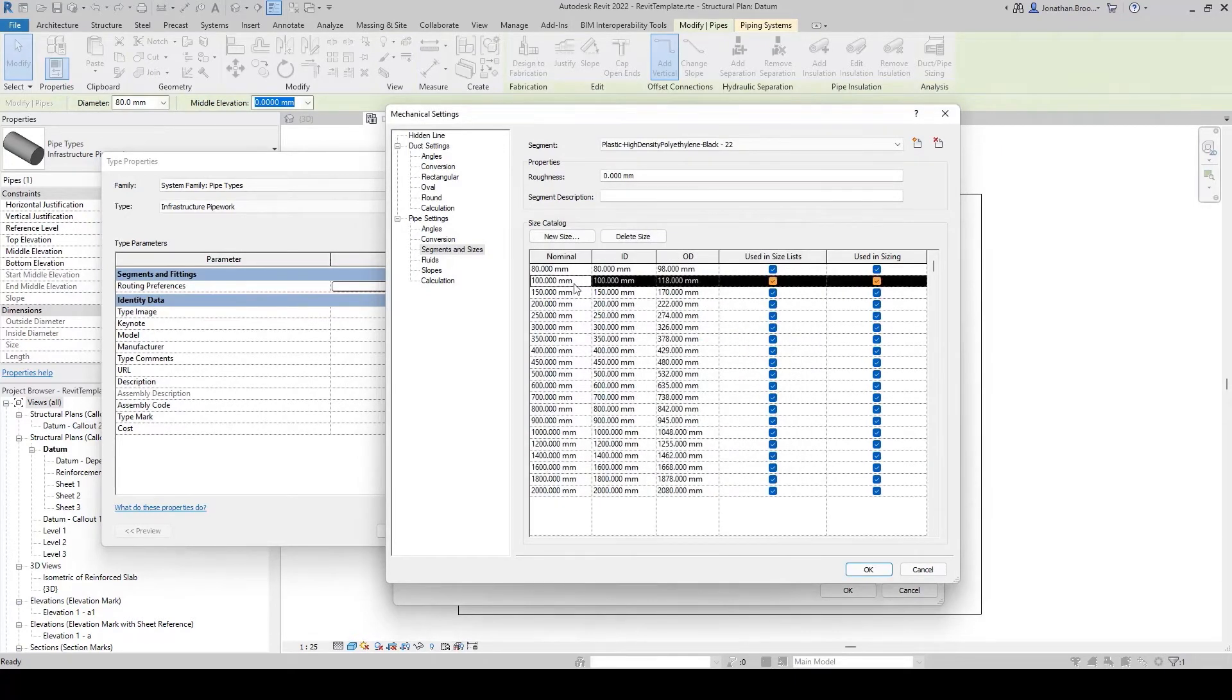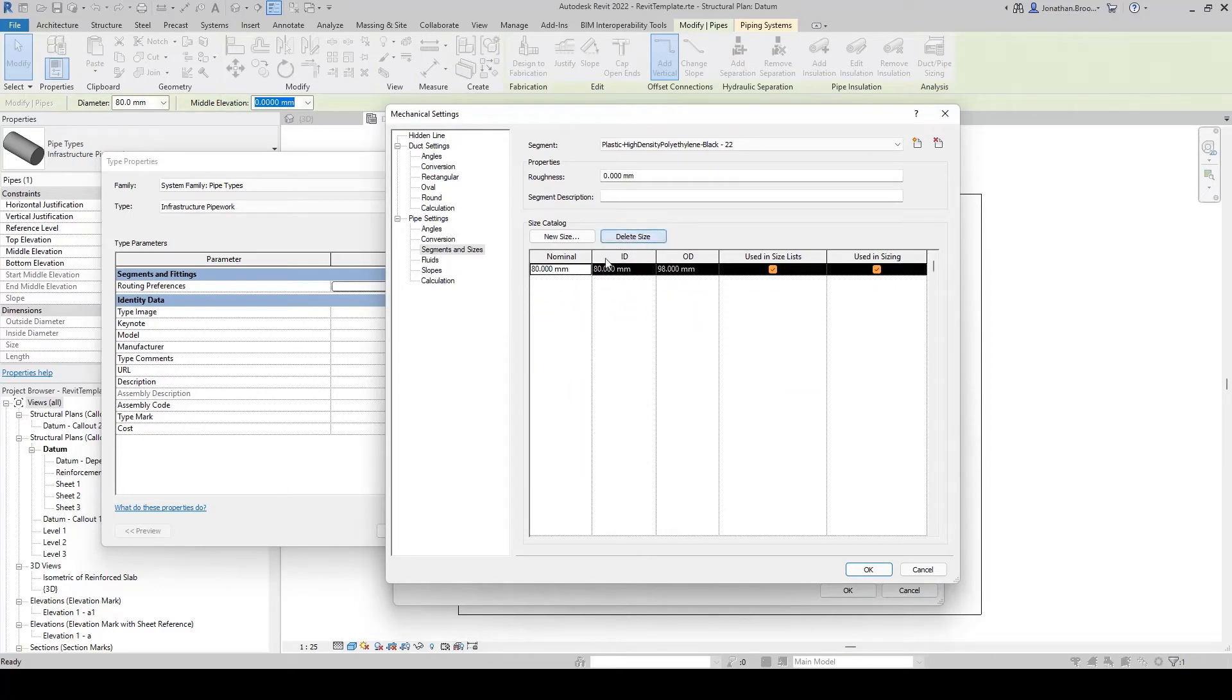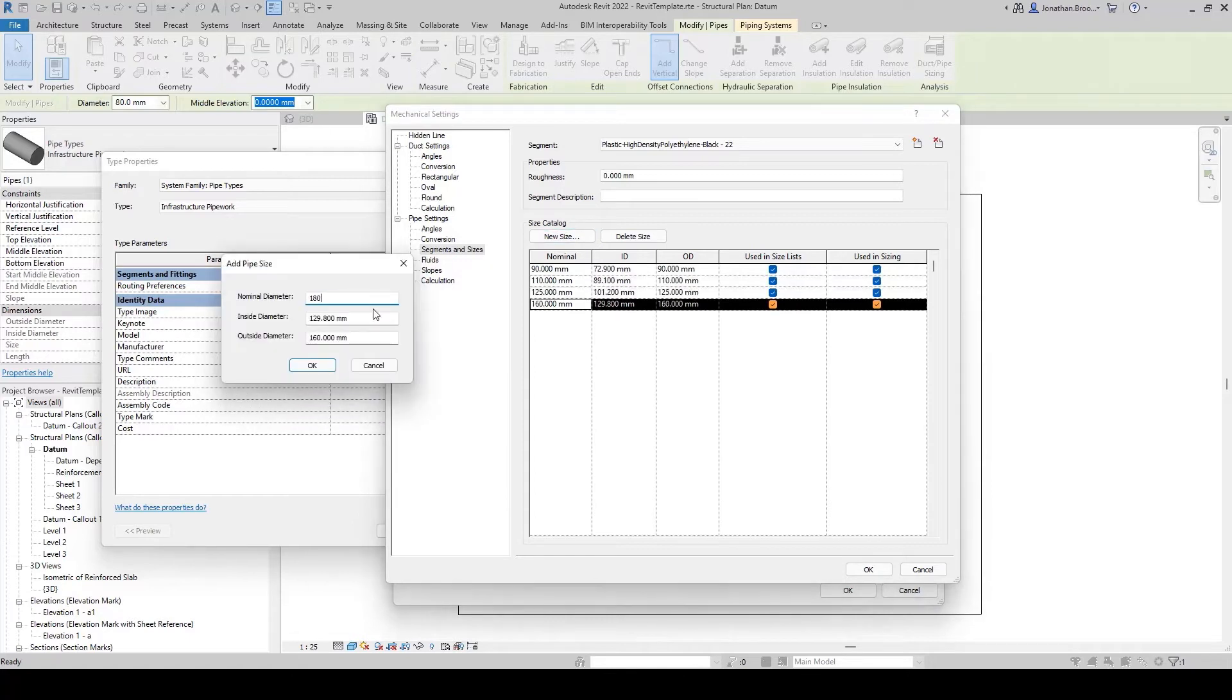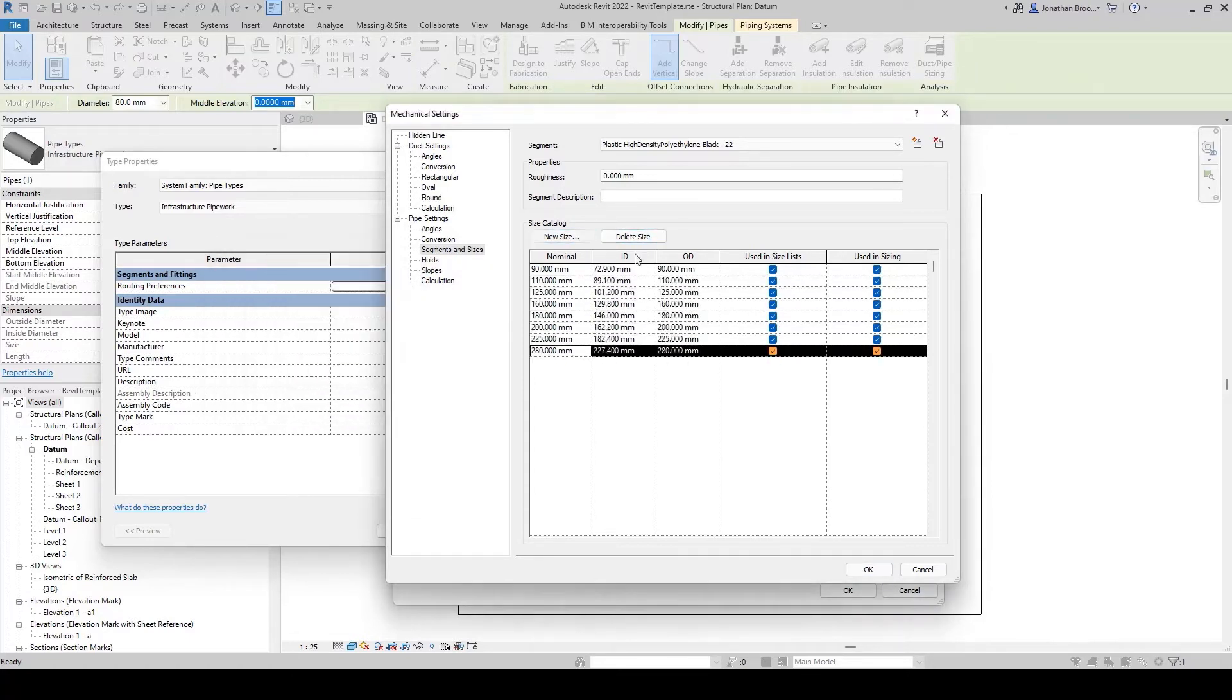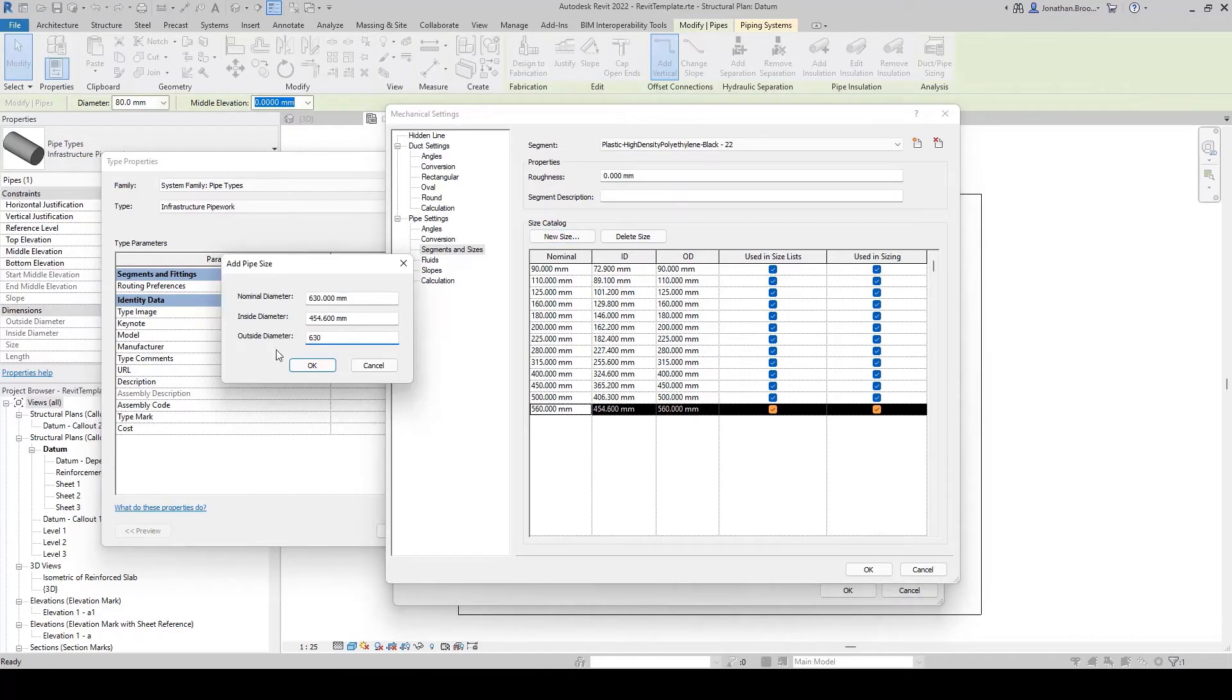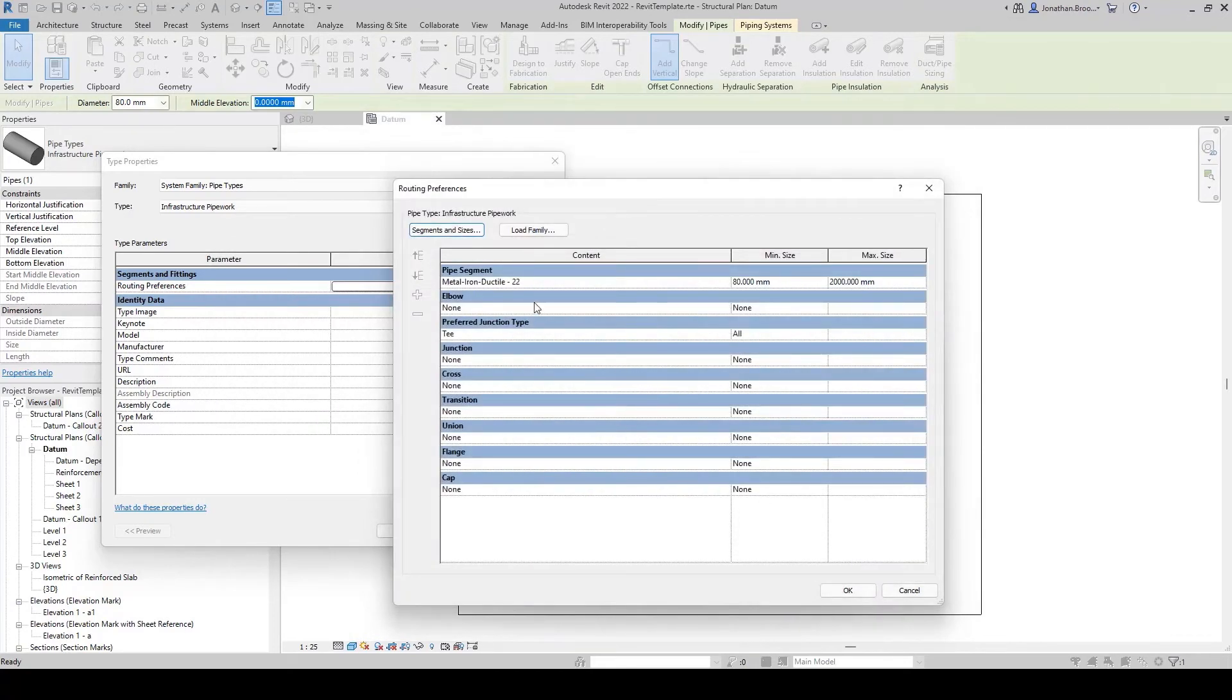For a complete customized list, we can delete the default sizes provided and start including our own. What we need to define here is the nominal, internal and outer diameters by repeatedly using the new size button. In this example, we're adding polyethylene pipe sizes taken from a specific manufacturer's website. Once all the pipe sizes have been included, we can hit the OK button.